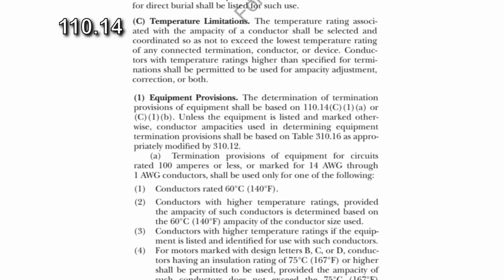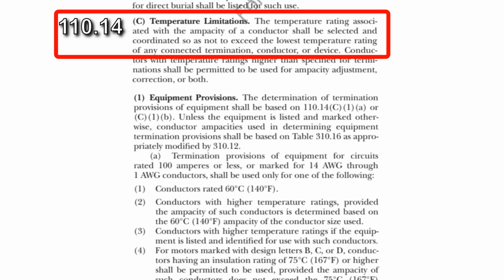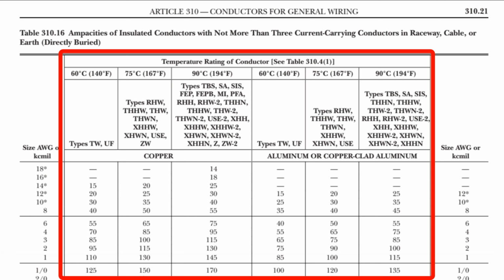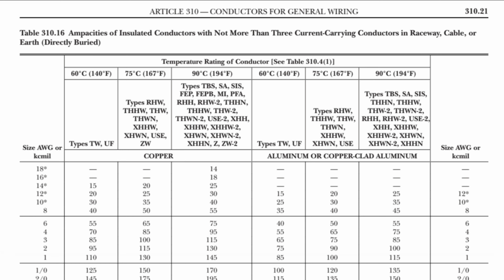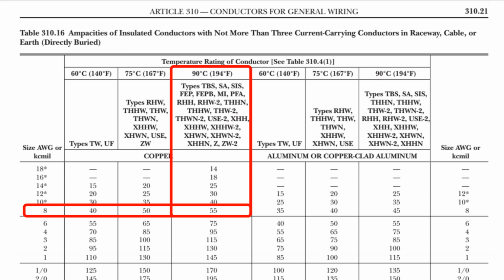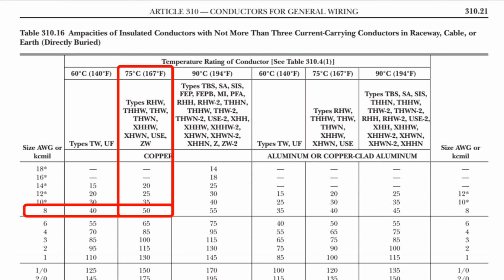Let's see how 110.14(C) requires us to coordinate the conductor and terminal temperature limitations. First part, temperature limitations. The temperature rating associated with the ampacity of a conductor shall be selected and coordinated so as not to exceed the lowest temperature rating of any connected termination, conductor, or device. So the conductor has a temperature rating and the terminations on devices we're wiring have temperature ratings. And when we connect them, we need to respect the weakest links in the chain. For example, a conductor that's rated 55 amps at 90 degrees C can't be applied at 55 amps when it's connected to a 75 degrees C terminal. The conductor will have to be derated to its ampacity listed under the 75 degree column in the ampacity tables.